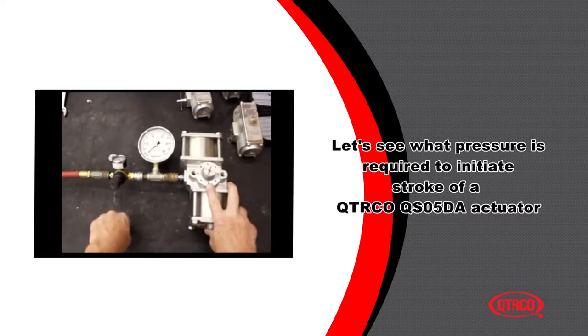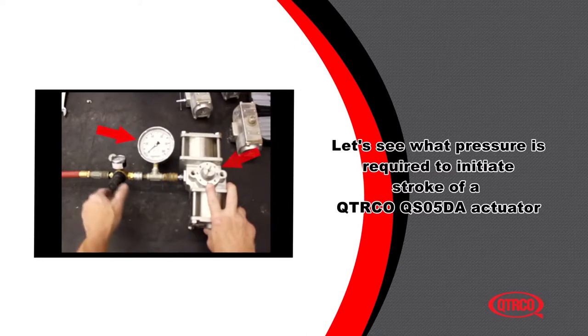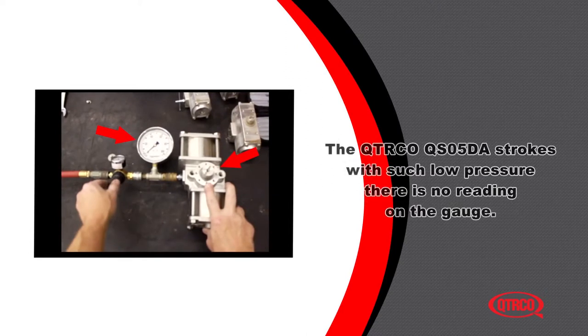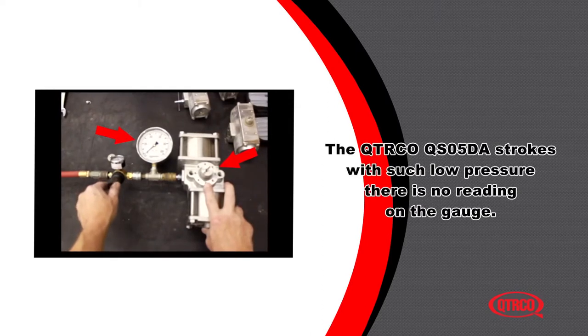Let's see what pressure is required to initiate stroke of a QTRCO QS05DA actuator. The QTRCO QS05DA strokes with such low pressure, there is no reading on the gauge.